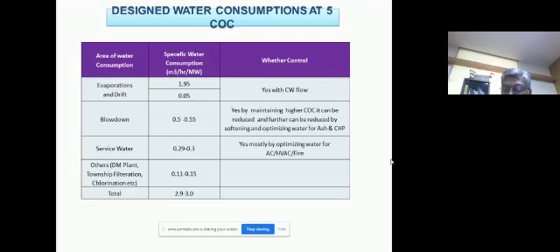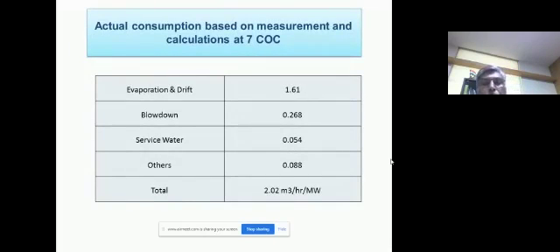Now I am coming to what we are actually achieving. This is the actual water being consumed at our plant, and instead of 5 COC, we have gone to 7 COC. Therefore, a lot of saving because of high concentration. And this is the blowdown and service water, and the total water is 2.02 meter cube per hour per megawatt. If you believe that it can be achievable, then you can achieve it. Otherwise, if you think that it is not, then you cannot. So we have to believe. We are even going below 2 meter cube per hour per megawatt, that is the aim we have.